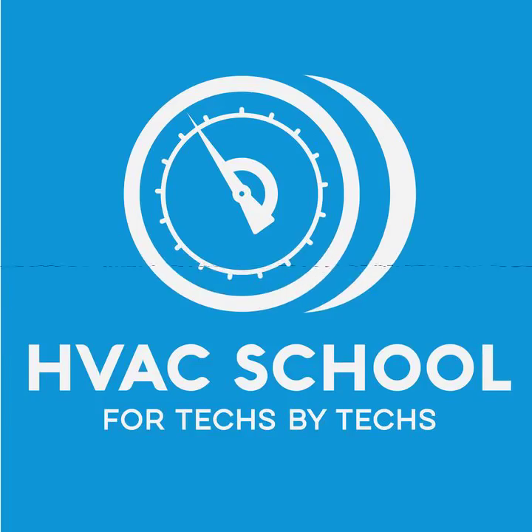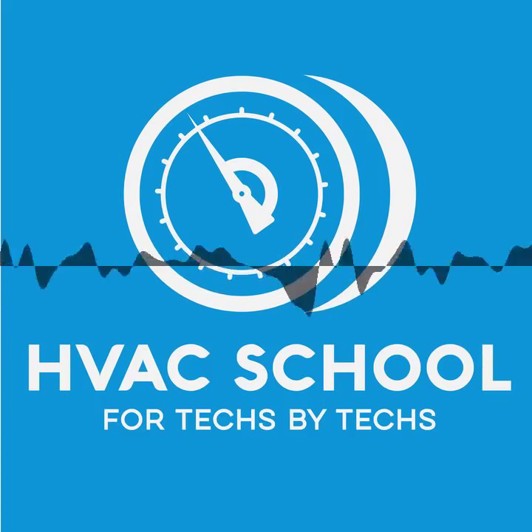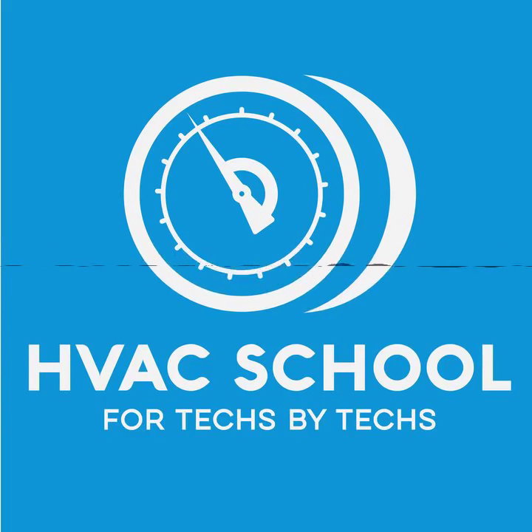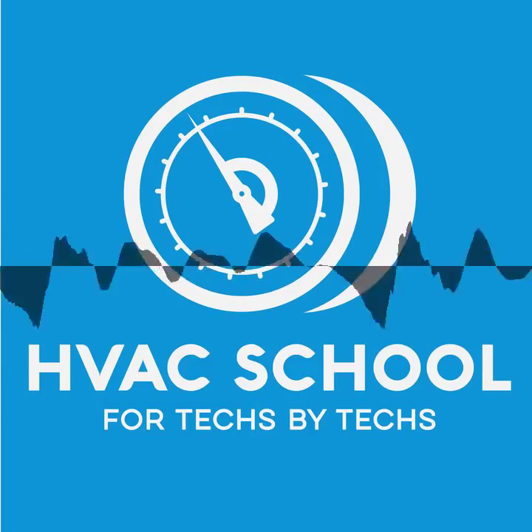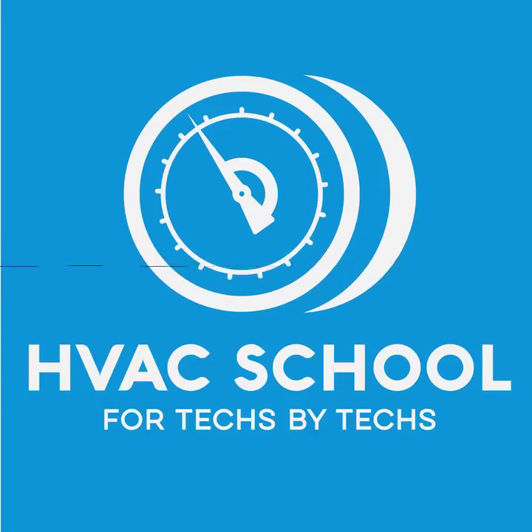Now, here's what I'm not doing. I'm not looking for a specific ohm reading across that coil, because I don't know what ohm reading that coil should be unless I have another one of those exact same contactors that I can compare to. I don't know what the correct ohm reading is. So here's what a lot of technicians do in this case. And again, this gets back to the point of this, some basic education on how to use a meter, reading resistance and voltage, voltmeter and ohm meter. But what I'm not going to do is read across that thing and say, oh, it's reading 11 ohms. That sounds wrong to me.